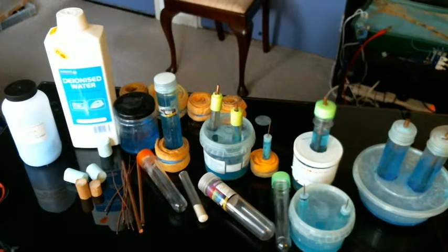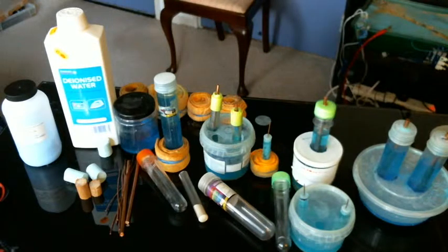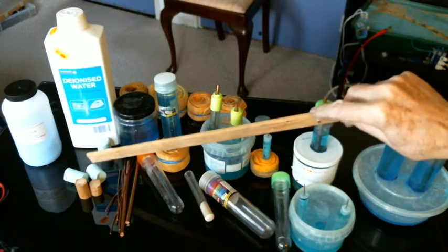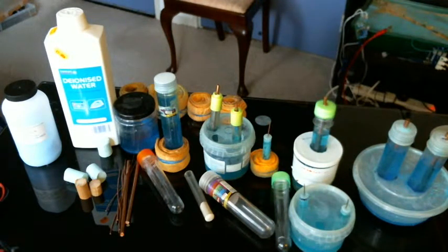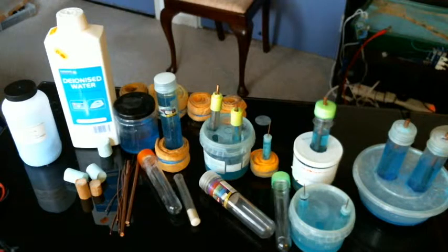To make your own copper sulphate electrode, you can take a short length of copper rod and a plastic tube. You can use wood or porous filler to make a plug, but ceramic material does last longer. Put the plug into the bottom of the tube and fill it with copper sulphate solution, with some crystals at the bottom to make sure it is saturated. Fit the copper through the lid of the tube and prepare it as a meter connection. That's it.